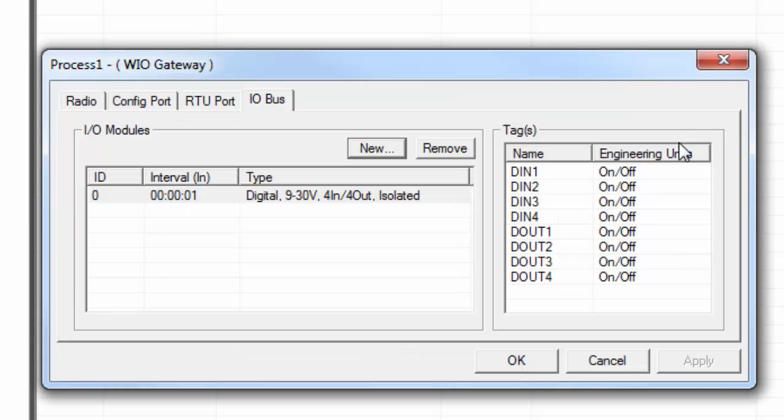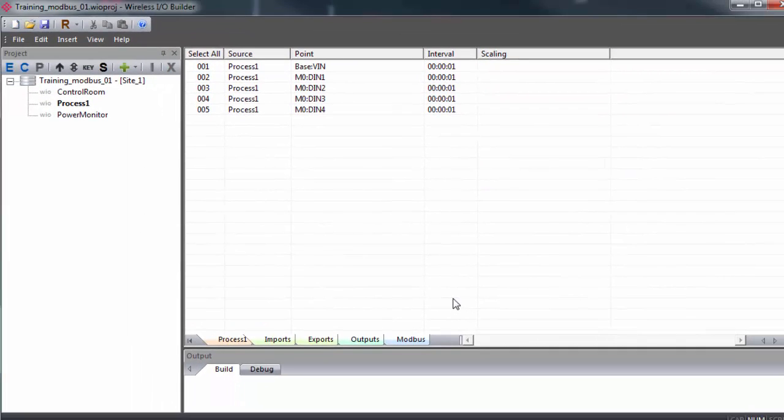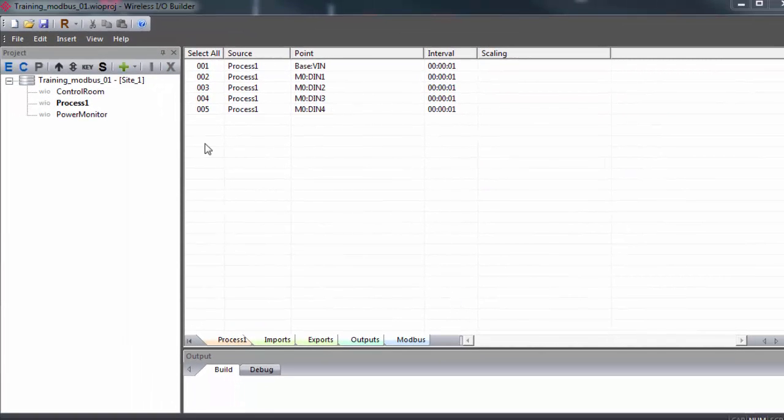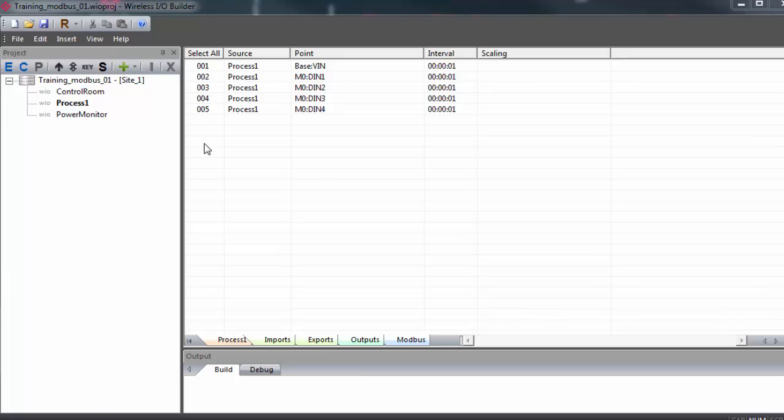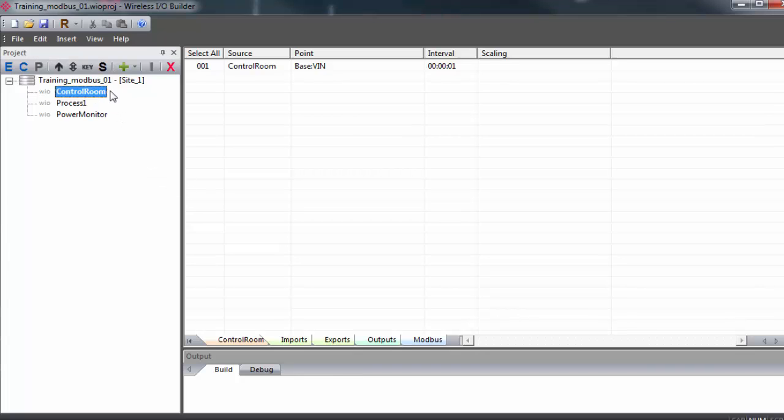In order to relay data from a third party Modbus master device to a point or output on the wireless IO network, a Modbus write function must be created in the primary gateway's Modbus table. So once this has been created, the point can be mapped to an output or shared with another device within the network. So we'll create a write function.